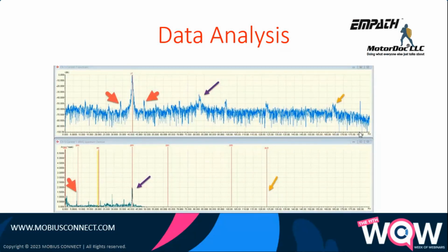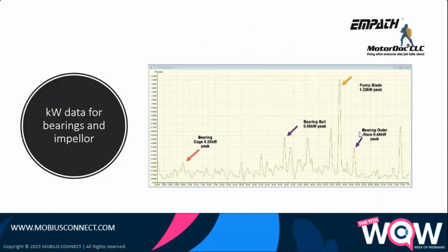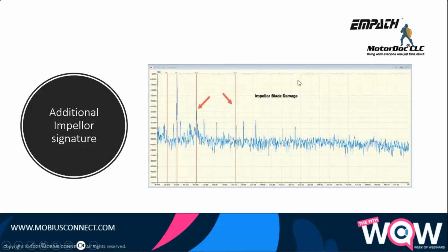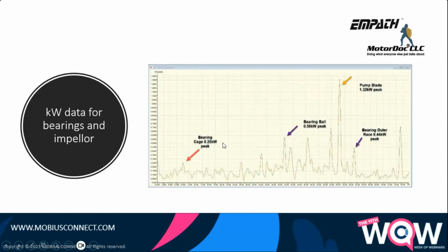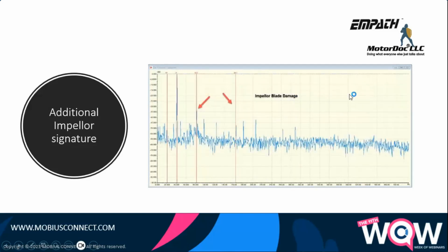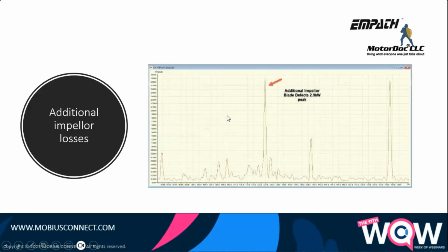When we do the analysis, we see blade signatures. We're seeing some other stuff. Going back to our kilowatts for that, we see some significant blade frequencies, as well as bearing cage, the bearing ball, and then the outer race. The inner race didn't show a significant peak, but those add up. Pump blade, turns out that we were showing these blade frequencies because there was a ding on the blade. When they were putting it together, they had to shave down the blade in order to get a better efficiency point. And somewhere along the way, they dinged one of the blades on the impeller. And that is the resulting loss. It was more significant than the failing bearings.